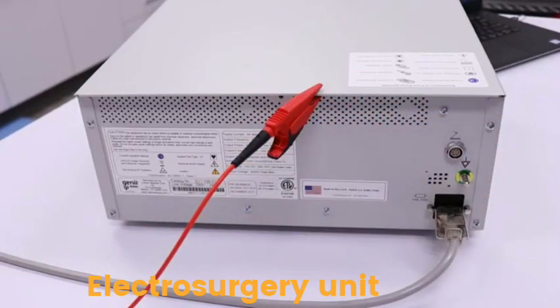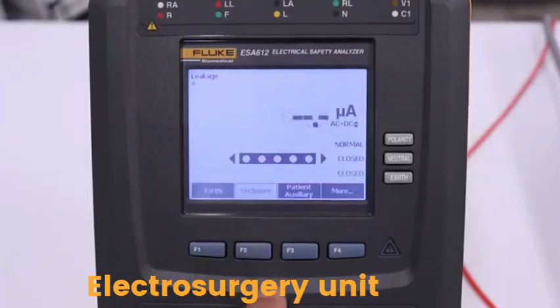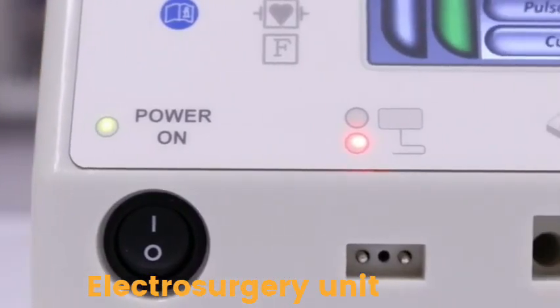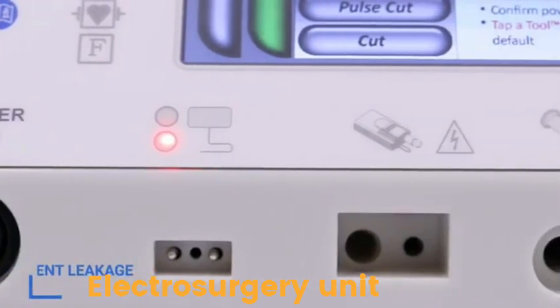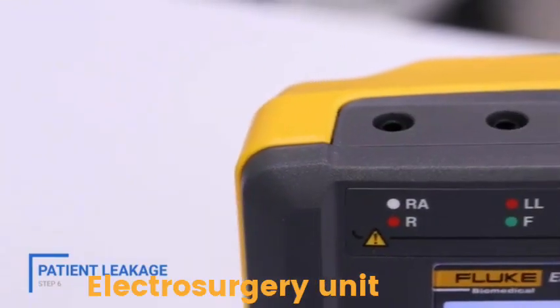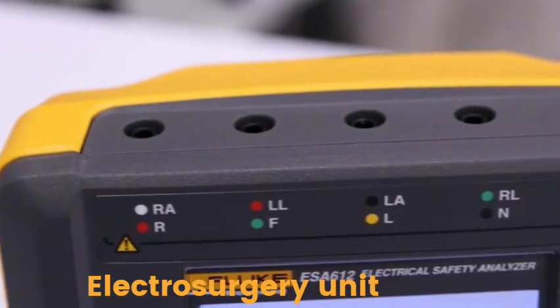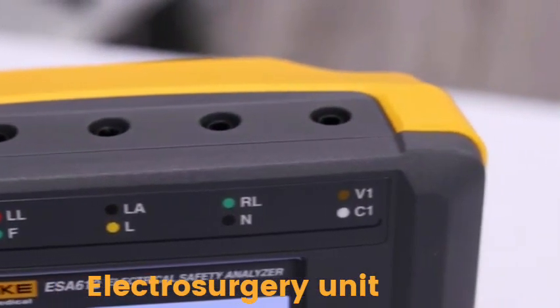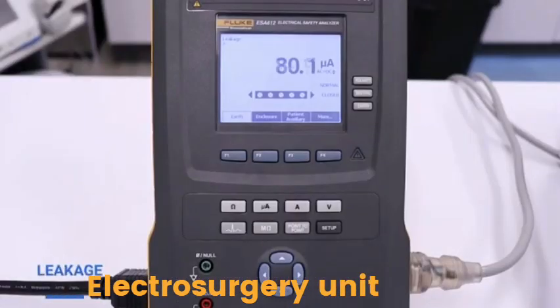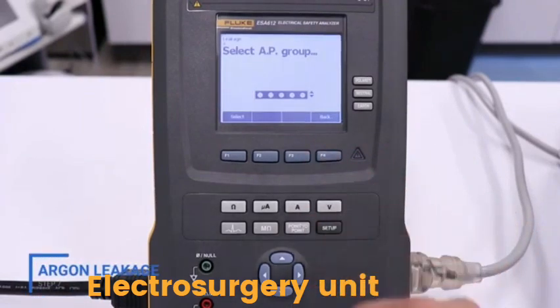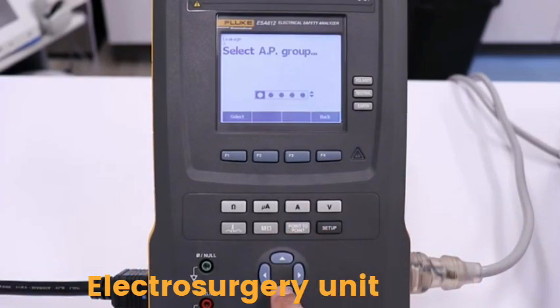Place the alligator clip on the upper panel. Press the F2 button on the ESA to select enclosure. Test for normal polarity closed condition and single fault open neutral condition. Patient leakage testing is performed using the receptacles on the top of the ESA. To enter the patient leakage mode on the ESA, press the F4 button to select More from the leakage menu.